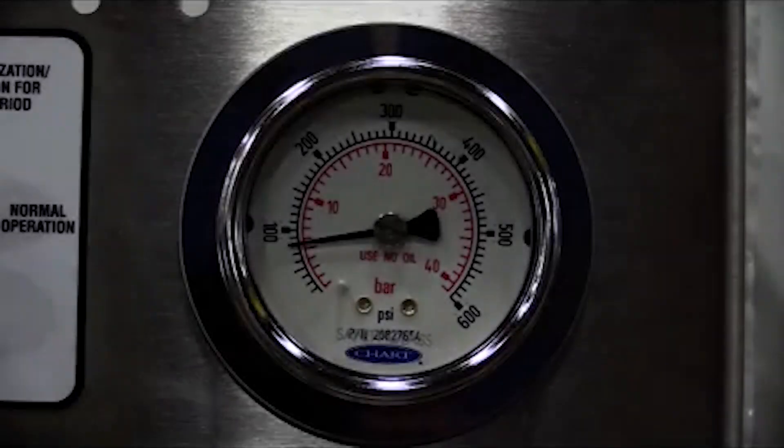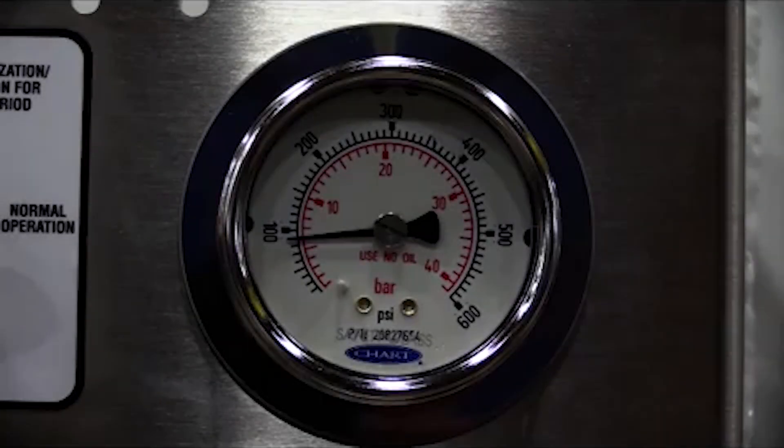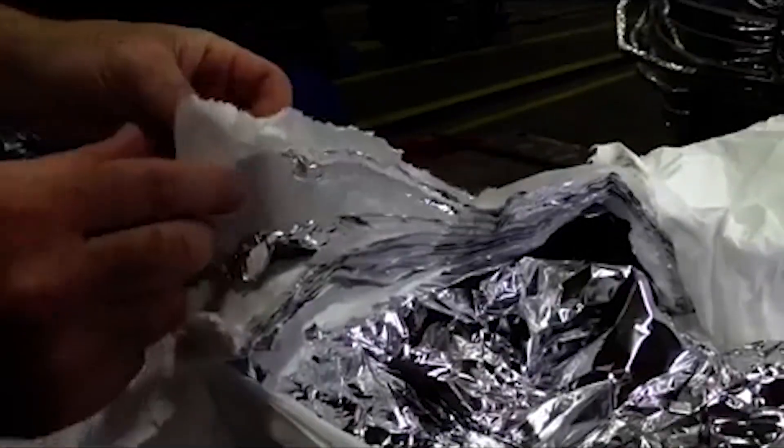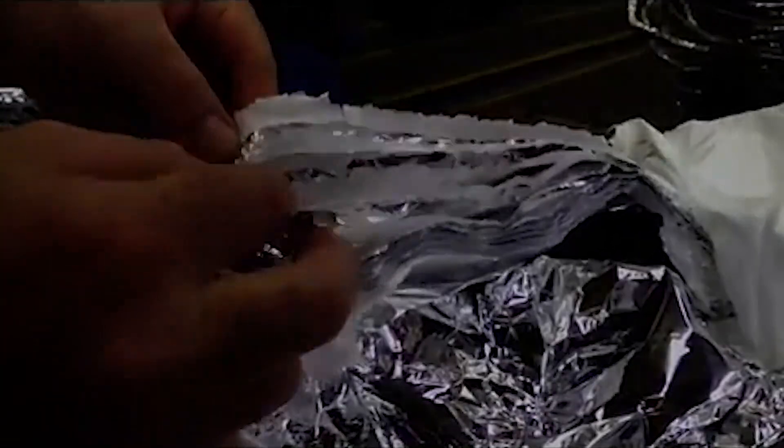NER is a performance consideration that must be balanced against product and withdrawal rates. If use rates are too low, the heat from the NER will cause heat and pressure to build up in the tank. To control this heat transfer, Chart uses a proprietary multi-layered super insulation system.